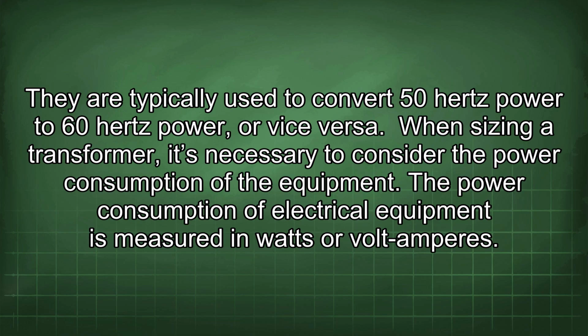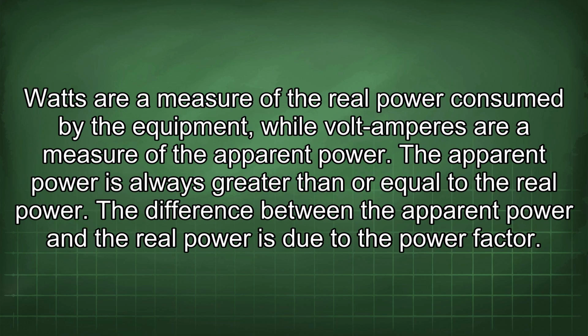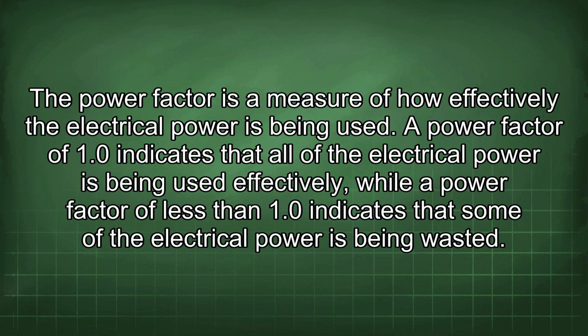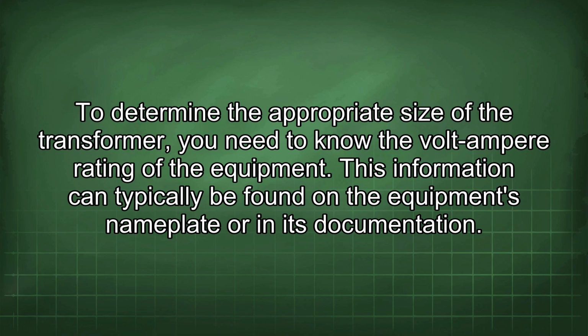When sizing a transformer, it's necessary to consider the power consumption of the equipment. The power consumption of electrical equipment is measured in watts or volt-amperes. Watts are a measure of the real power consumed by the equipment, while volt-amperes are a measure of the apparent power. The apparent power is always greater than or equal to the real power. The difference between the apparent power and the real power is due to the power factor. The power factor is a measure of how effectively the electrical power is being used. A power factor of 1.0 indicates that all of the electrical power is being used effectively, while a power factor of less than 1.0 indicates that some of the electrical power is being wasted. To determine the appropriate size of the transformer, you need to know the volt-ampere rating of the equipment.